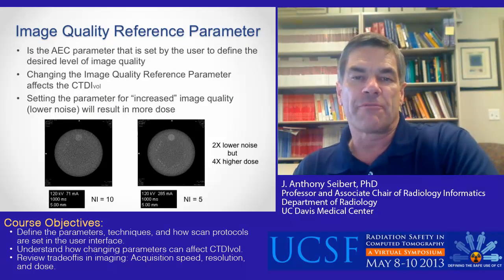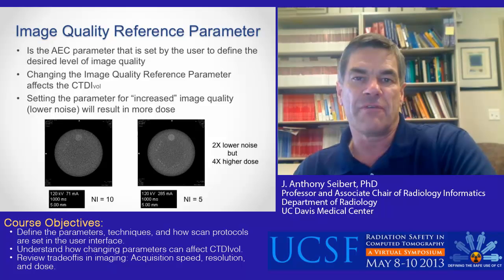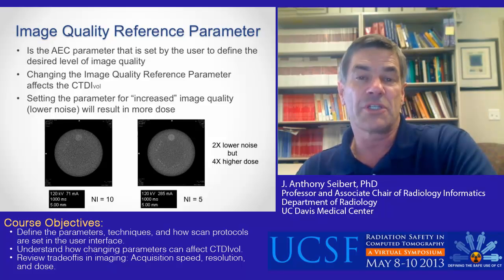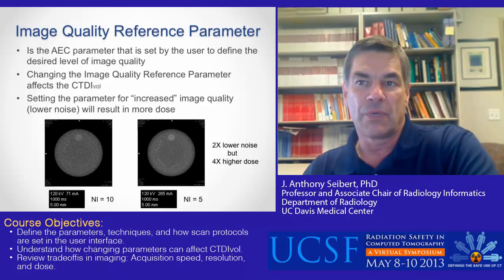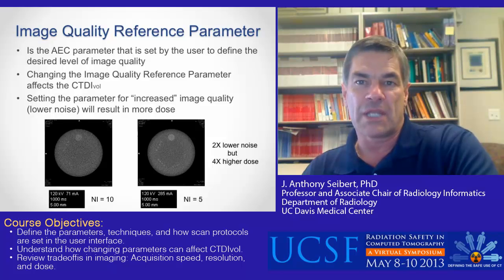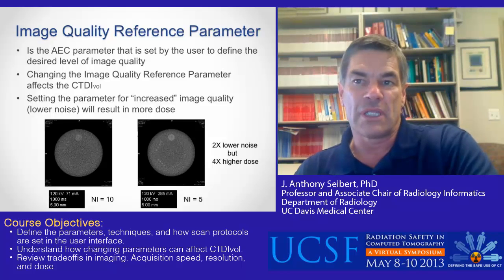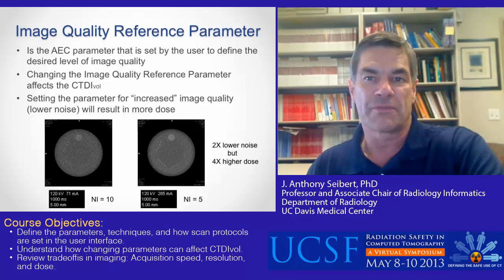The image quality reference parameter defines the level of tube current and thus the noise in the reconstructed image. One manufacturer uses a parameter called noise index, which is an estimate of the standard deviation of CT numbers in a reconstructed image. The variance of the image is directly proportional to the number of x-rays detected, and the standard deviation is equal to the square root of the variance. When changing the noise index to lower values to achieve lower noise, image quality improves but dose increases by the square of the amount of noise decrease. For example, an image acquired with noise index equal to 10 requires 71 mAs. If the goal is 2 times lower noise, the noise index can be set to 5, and the mAs increases to 285, resulting in much better image quality but with 4 times the CTDI vol.